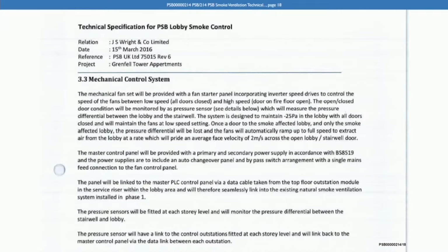So it's right, isn't it, that when the system's pressure sensors cause the fans to ramp up after the door opens, they ramp up to their full 100% high-speed setting, yes? That's correct. And if the door is then closed, the stair door's closed, and the pressure differential is restored, what speed would the fans then drop back to? The predetermined speed that I'd set during commissioning. And what predetermined speed did you set?